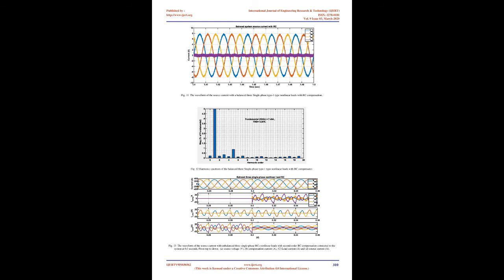A. Balanced three single-phase nonlinear loads without compensation. Balanced three single-phase nonlinear RC loads are connected to the three-phase source system to collect the harmonic spectrum of the RC loads. The waveforms in Fig 9 showed that the source current is highly distorted for single-phase type 1. Moreover, the neutral current has the same magnitude as the phase line currents, but the neutral line carries zero sequence harmonic distortion. The total source current harmonic distortion, THDi, was found to be 80.32%.